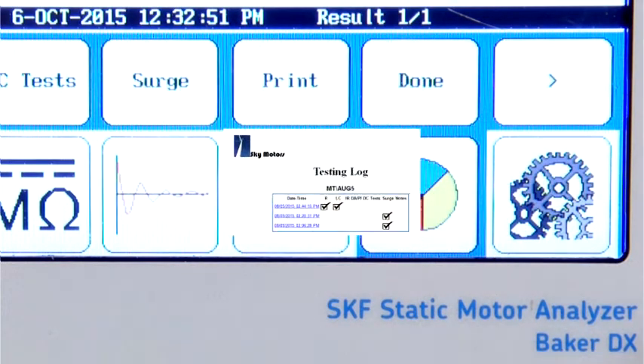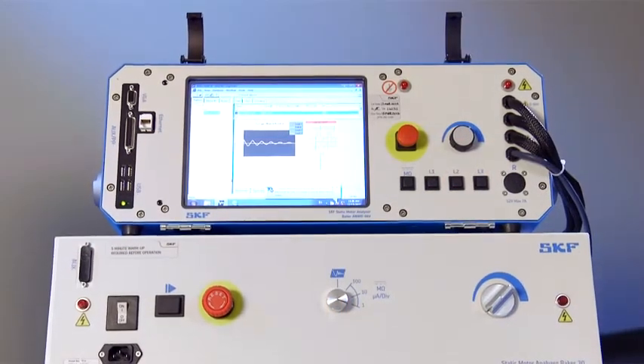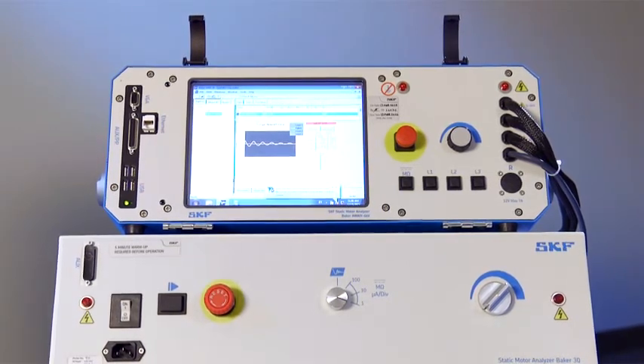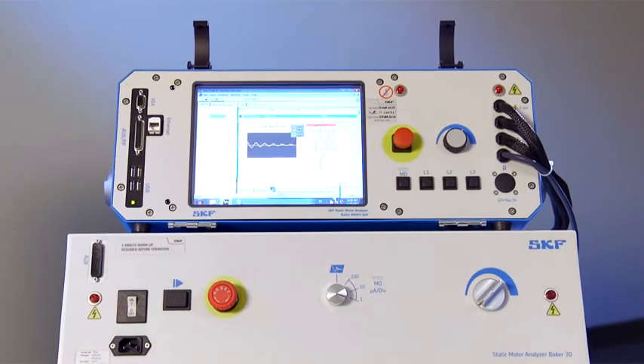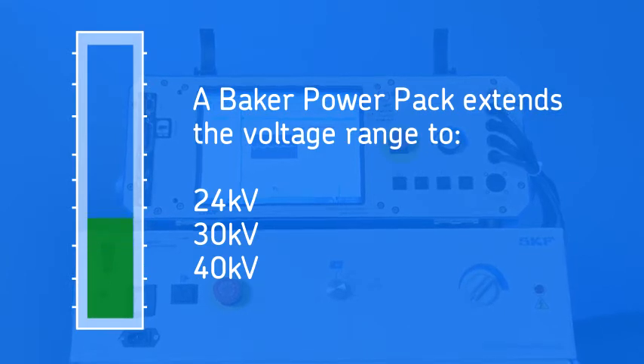Reports can also print directly from the DX. Company logos can be added to the report. For testing of very large motors or form wound coils, the voltage range of the SKF static motor analyzers can be extended using a power pack. These solutions boost the output voltage to 24kV, 30kV, or 40kV for the ground wall insulation DC tests and the turn-to-turn insulation surge test.